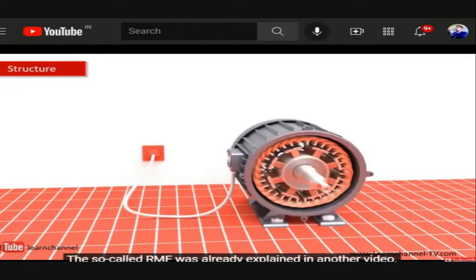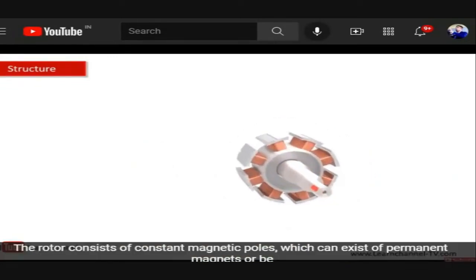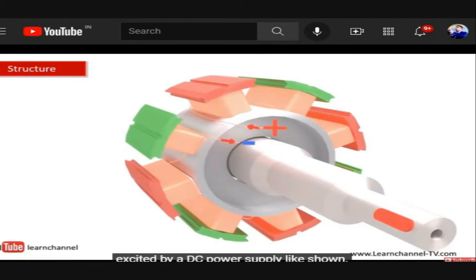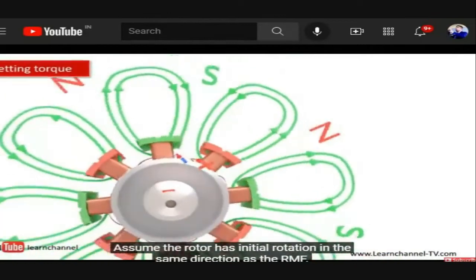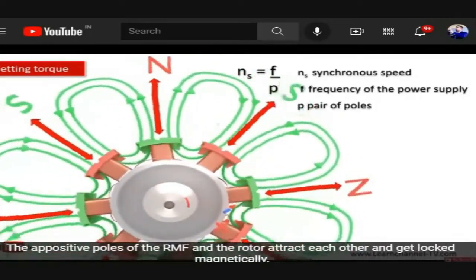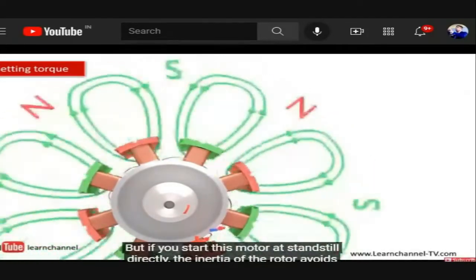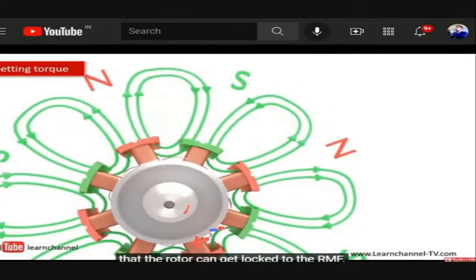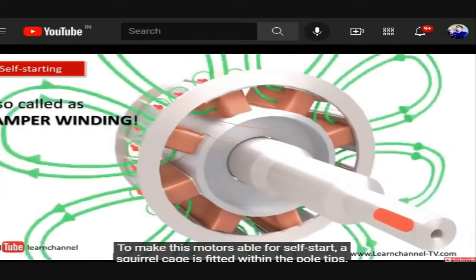The rotor consists of constant magnetic poles, which can be permanent magnets or excited by a DC power supply. If the rotor has initial rotation in the same direction as the RMF, the opposite poles of the RMF and the rotor attract and get locked magnetically. However, if the motor is started at standstill, the rotor inertia prevents it from getting locked to the RMF, making a squirrel cage necessary for self-starting.